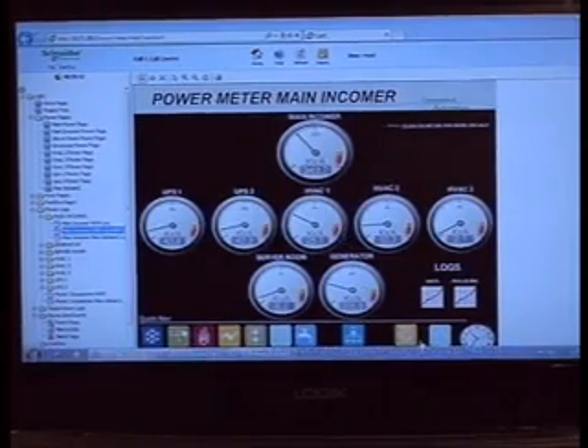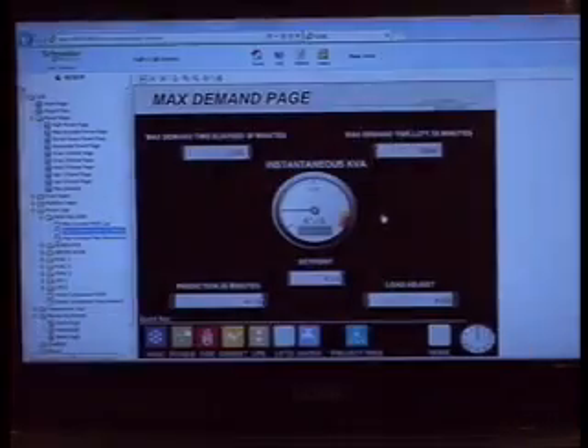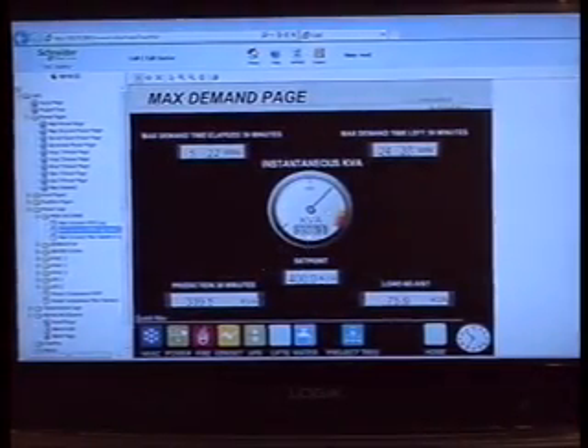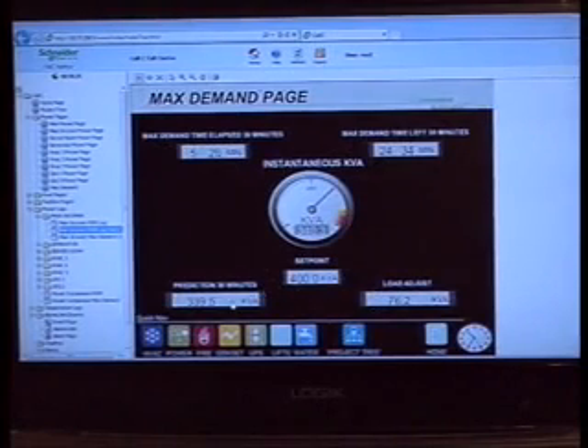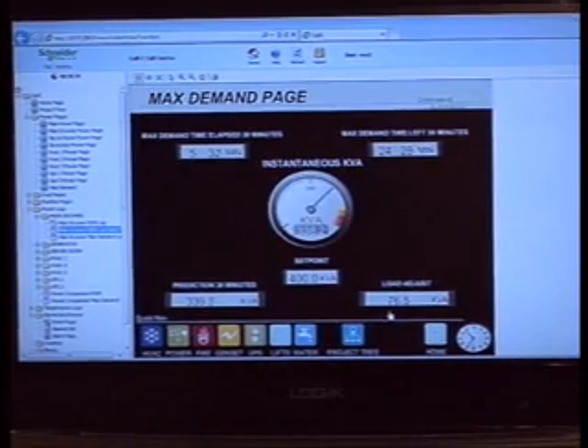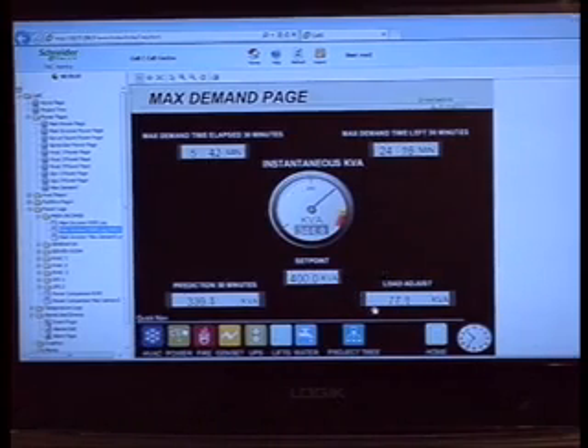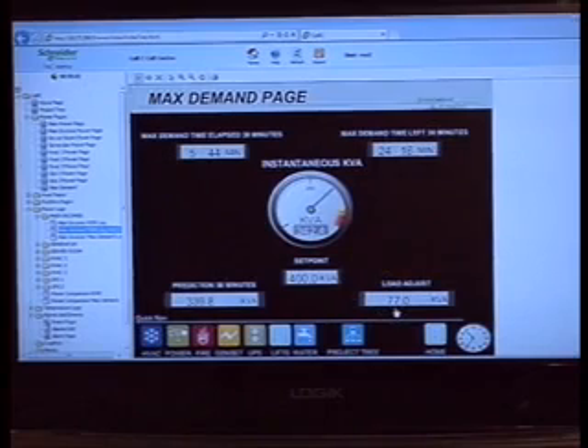What we do with this information is what we call a peak demand prediction. So based on your instantaneous values within your half-an-hour period, we can predict your half-an-hour average. Based on your half-an-hour average, we can control equipment to reduce your peak demand charge. By controlling this equipment, we're not going to save you kilowatts, but we're going to save you kVA in your peak demand charge. So what we're doing is shifting load. Once this value gets close to zero or negative, that means we must shift the load. So we send a signal to the chillers, and the chillers must throttle back, release a little bit of load, just for a 5-minute period, just until that peak is gone, reducing your kVA, reducing your cost at the end of the month.